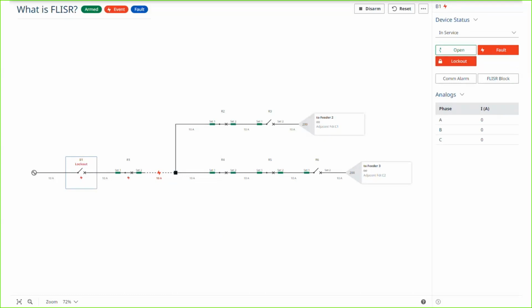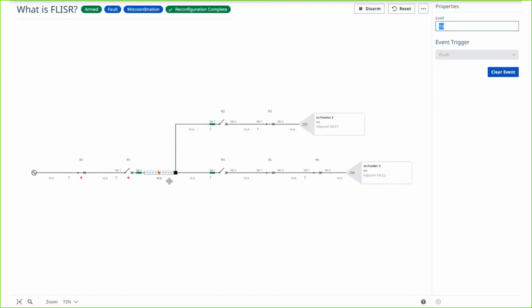Now you have a choice. If you had written some sort of script, you may find that the fault is in between breaker 1 and recloser 1, which is wrong. It's downline of recloser 1. So FLISR's job is to recognize that that is a miscoordination, and it can correct that miscoordination automatically. The fault is in the same spot as it was in the last example.